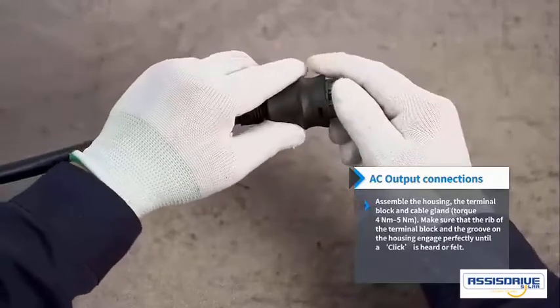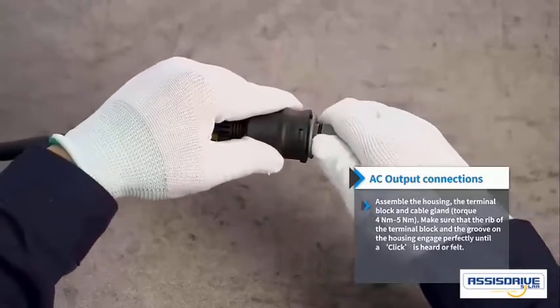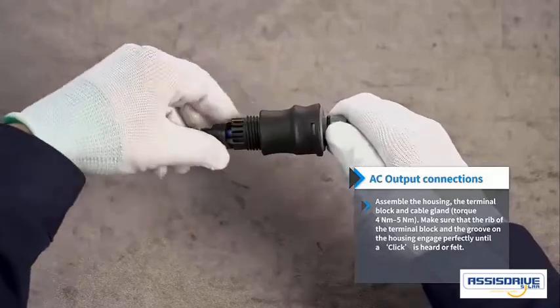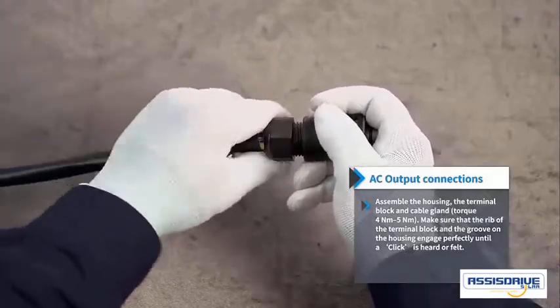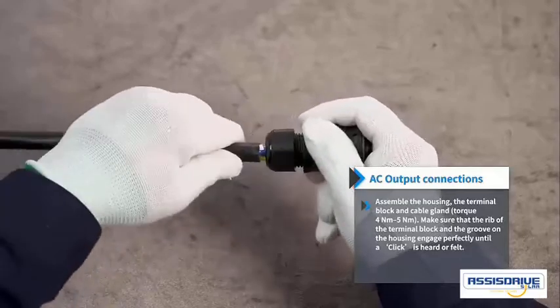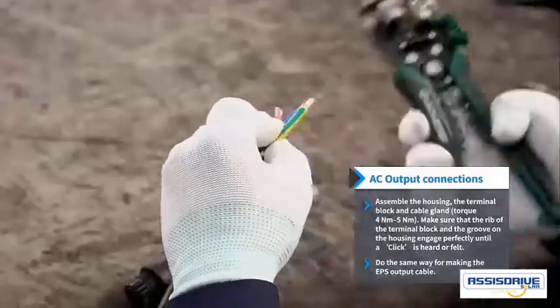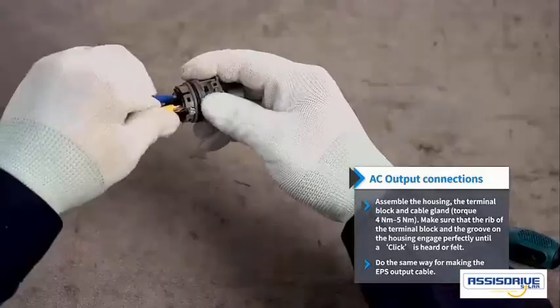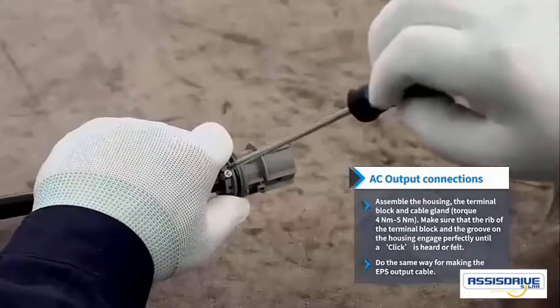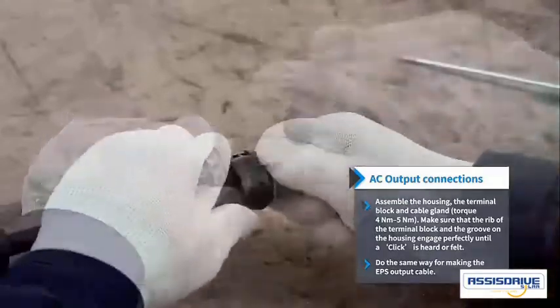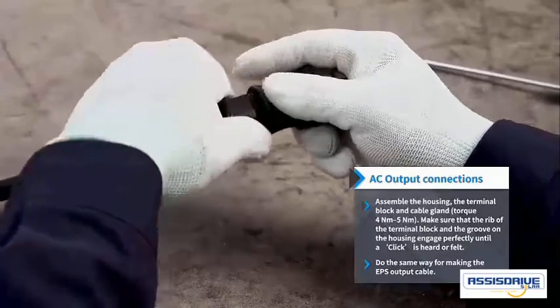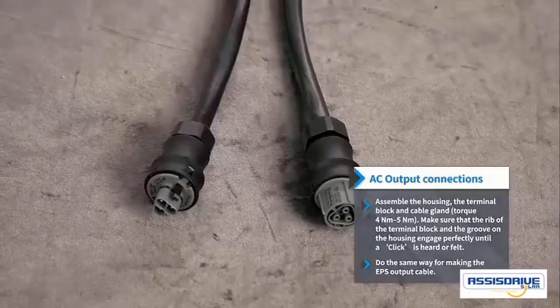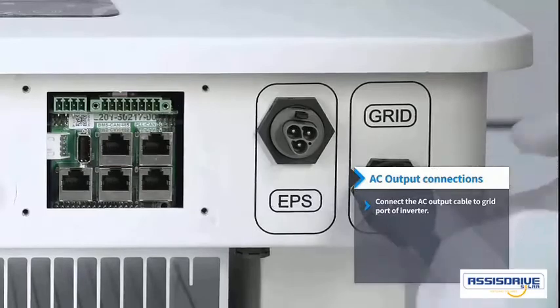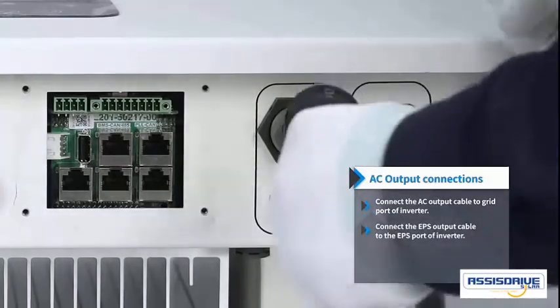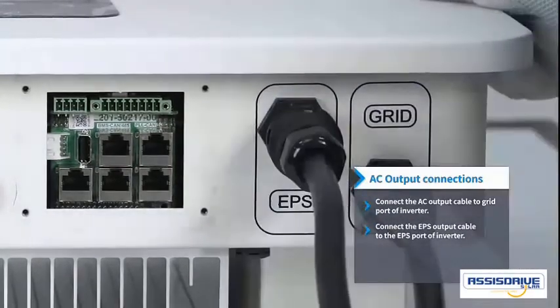Assemble the housing, the terminal block and cable gland. Torque 5 Nm. Make sure that the rib of the terminal block and the groove on the housing engage perfectly until a click is heard or felt. Do the same way for making the EPS output cable. Connect the AC output cable to grid port of inverter. Connect the EPS output cable to the EPS port of inverter.